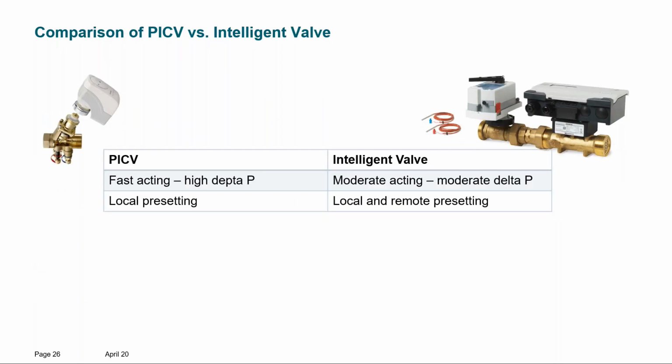Basically, in the starting point, an intelligent valve solution is an electronic PICV, but it acts like a PICV. There are some slight differences, like in regards of how fast this dynamic balancing acts. The electronic solution acts a little bit more moderate. The PICV is very fast. The intelligent valve solution might not be able to solve very, very high delta P's like PICVs today, but it solves moderate delta P's.